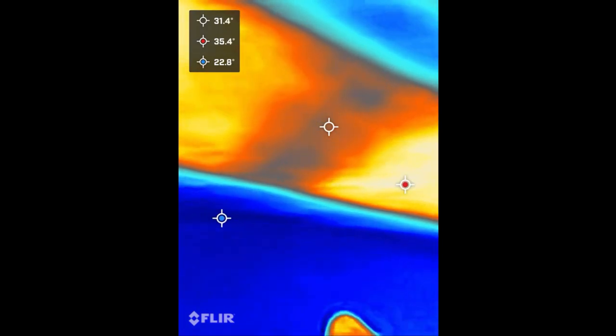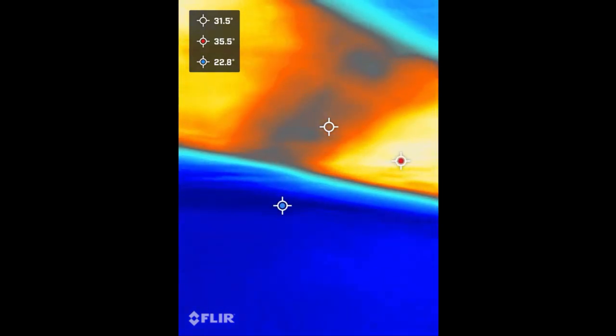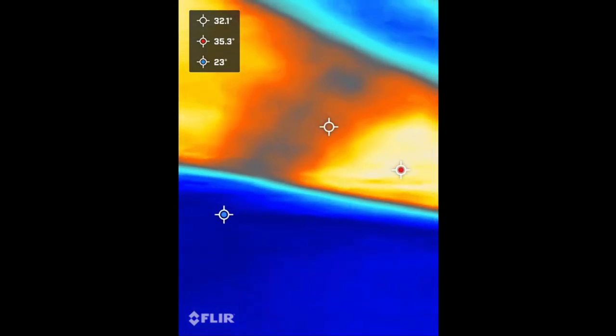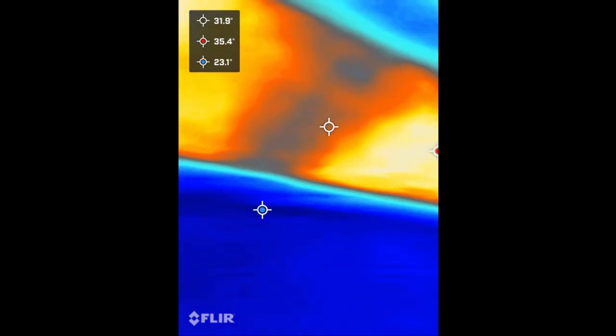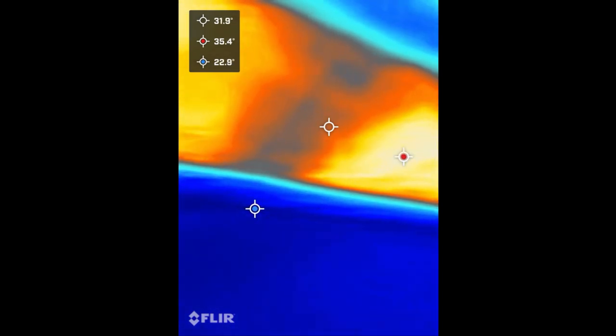There's definitely some degradation in a couple of the mats - one showing 31 where the mat is showing 35 degrees. So what would cause part of the mat on two or three of them not to work properly?